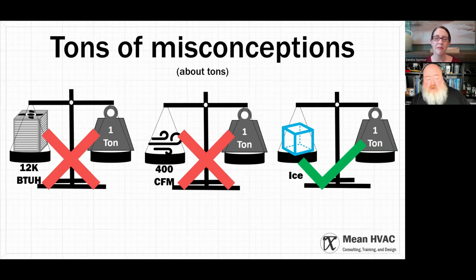You will hear the term ton a lot, and somebody's probably done this in one of their presentations or will do it again — the term ton is supposed to mean 12,000 BTUs and 400 CFM by the rules of thumb they teach in the HVAC industry. Neither of those things are true.